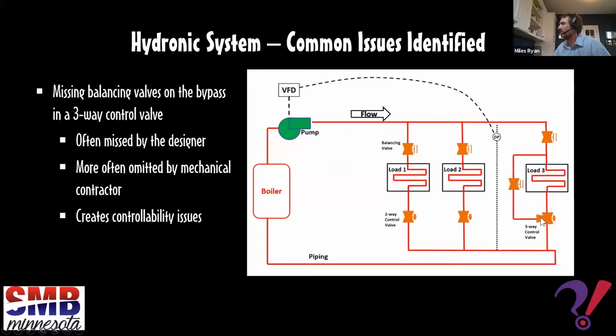So if this three-way control valve closes its port to load 3 because there's no reheating requirements, then we still have a path for the water to flow through. All right. Oftentimes, the balancing valve right here in this bypass leg is not installed. It's often missed by the designer. I've seen a lot of cases where the design firm is using copy and paste details for the last 40 years and putting them in the design package, and it's been missing that balancing valve for years. And then there are also cases when the mechanical contractors decide not to install it, even though it might have been spec'd to install. So let me give you an example of why this creates controllability issues.